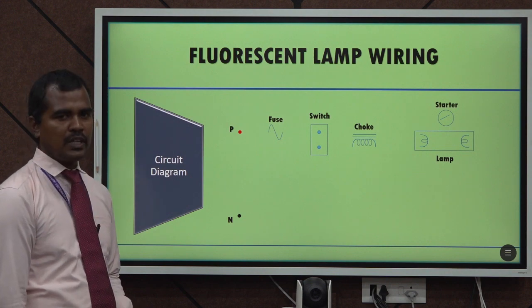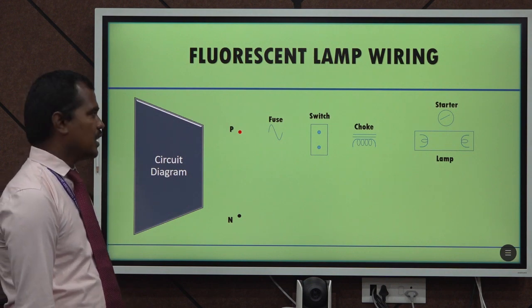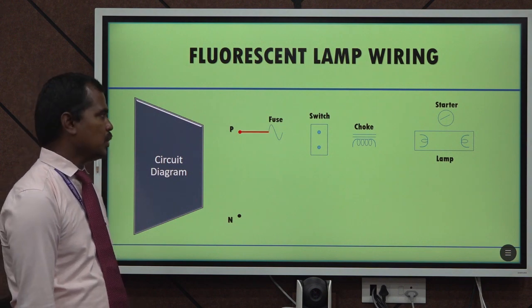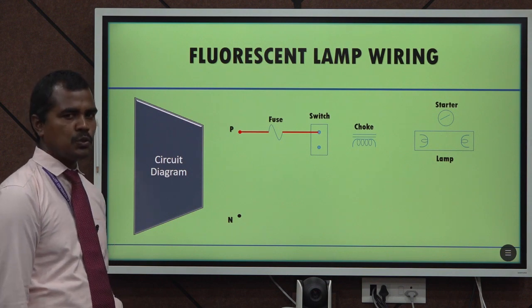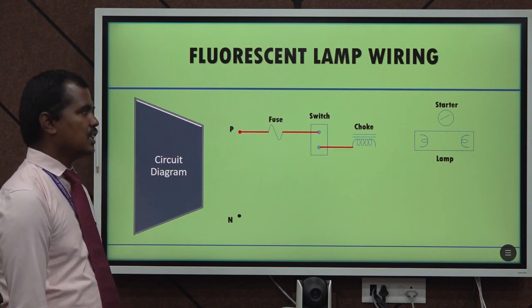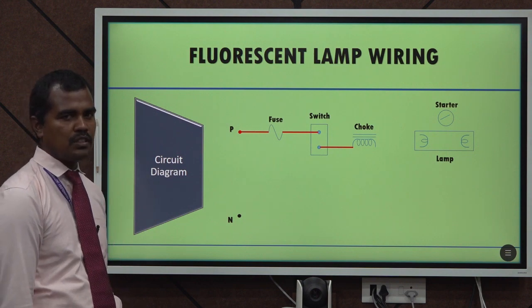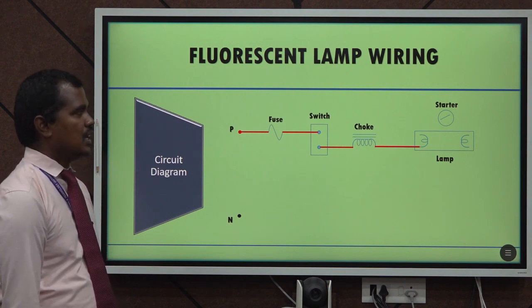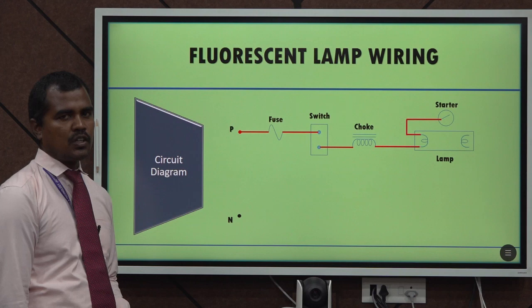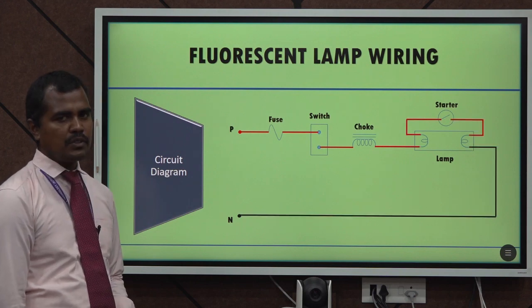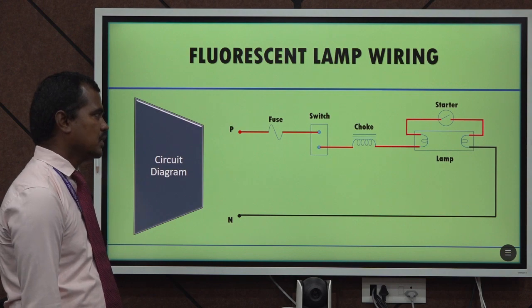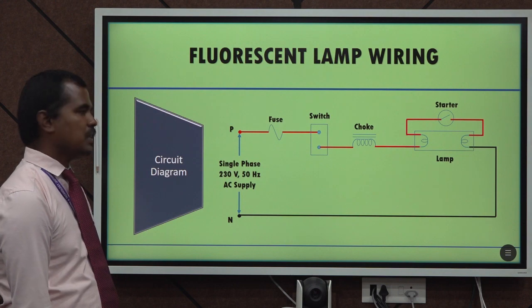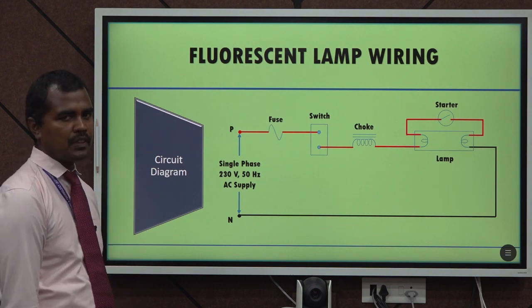So now I will explain how to connect. A wire from the phase to one end of the fuse and another wire from the other end of the fuse to one end of the switch. The other end of the switch is to be connected with the choke and the choke is connected with the fluorescent lamp. And the starter is to be connected across the lamp and the other end of the lamp has to be connected with the neutral point. So this is the entire connection diagram and it has to be connected with the single phase 230 volt AC supply.